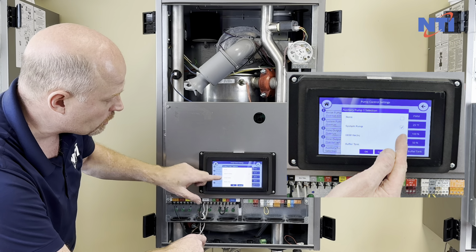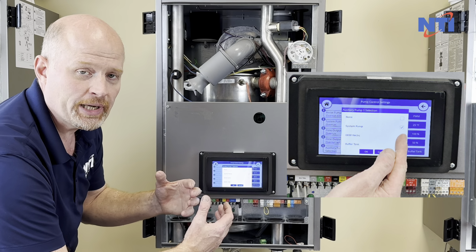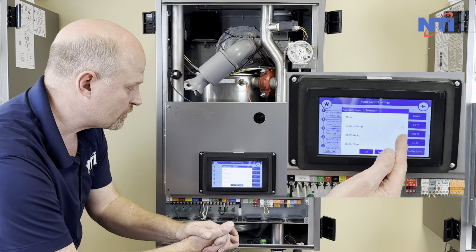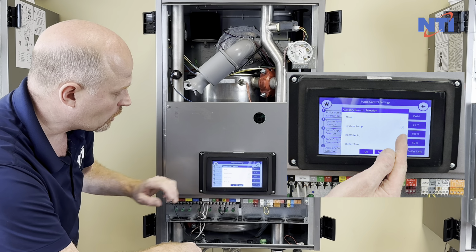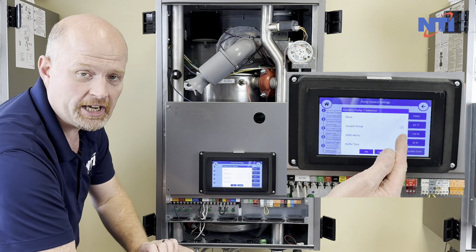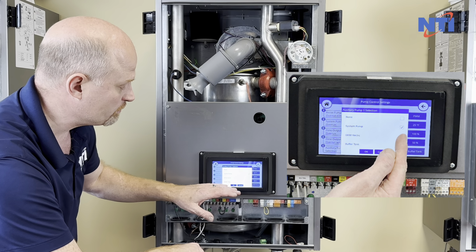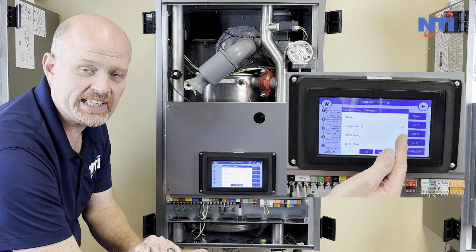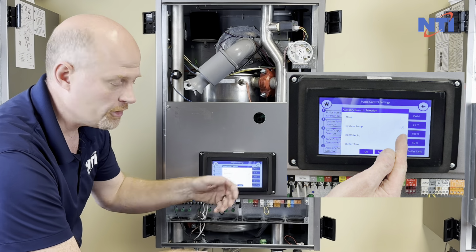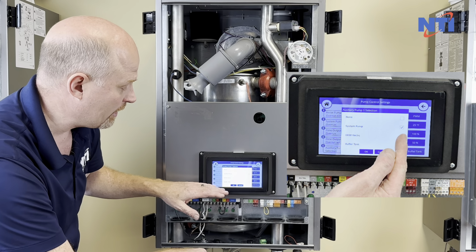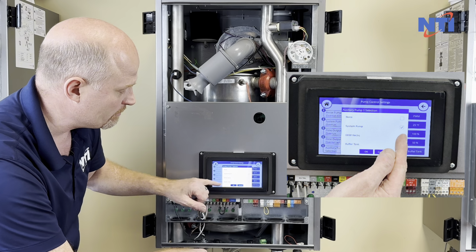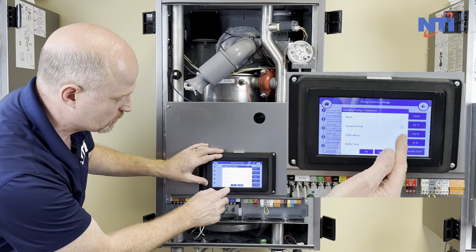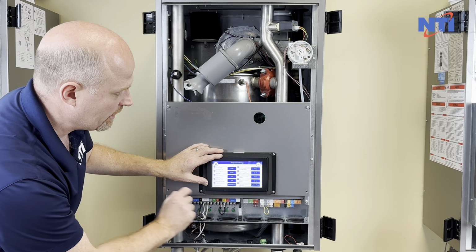Your domestic hot water recirculation, this is when you're doing an indirect water heater and you want to have recirculation to the fixtures in the building. And then you can also use it as a buffer tank pump. And a buffer tank pump works by looking at the buffer tank sensor. When the sensor drops to a set temperature, the pump will turn on, the boiler will reheat the buffer tank until the temperature in the tank is set and the buffer tank goes back off. Most commonly, people are going to use system pumps, so we'll leave it there, press OK.